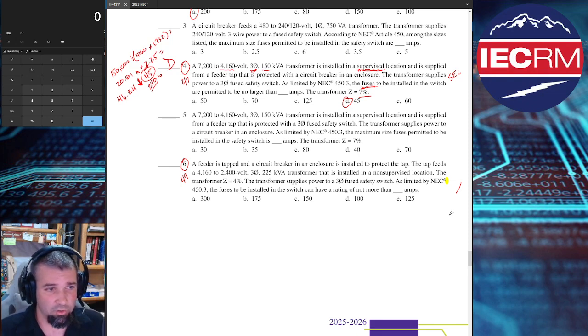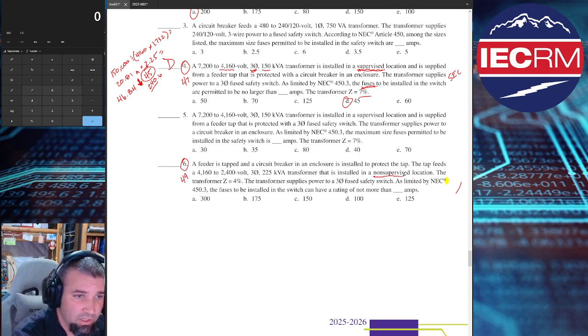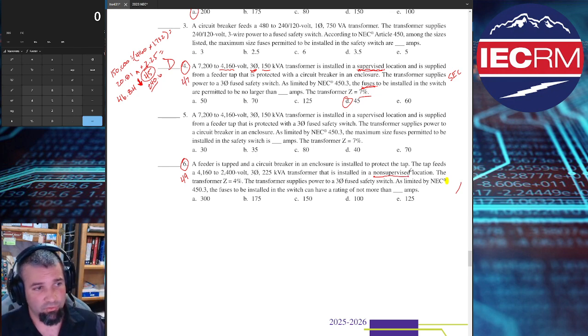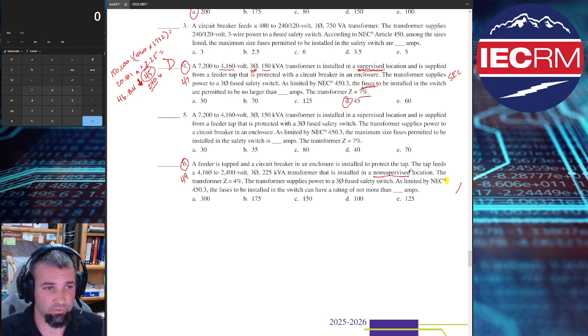A feeder is tapped and a circuit breaker and enclosure is installed to protect the tap. The tap feeds a 4160 to 2400 volt, 3-phase, 225 kVA transformer installed in a non-supervised location. The transformer impedance, or Z value, is 4%. The transformer supplies power to a 3-phase fused safety switch as limited by the NEC.